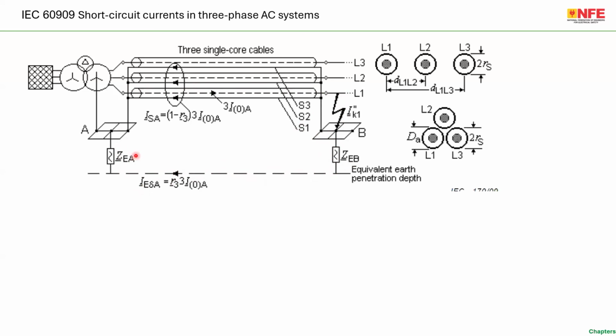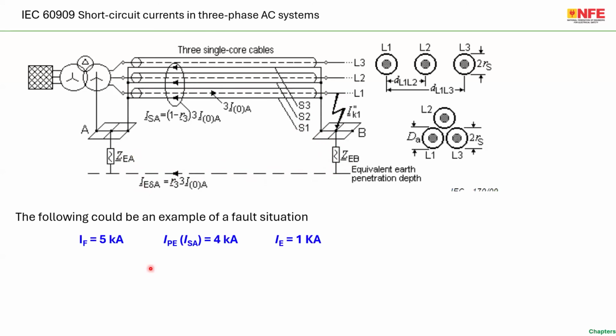So this is the only case, this is the only opportunity. Imagine, I'm just explaining an example. I will show you where you can find such information. Imagine the fault current is 5 kiloampere. The ISA, that means the current flowing through the shield conductor, is 4 kiloampere. Just for explaining to a not highly technical engineer, I use the word IPE, because in a lot of our presentations for low voltage we use the word IPE, the current through the protective earth conductor. Imagine that from station A to station B there is an overhead line with an earth conductor. Then 4 kiloampere goes through the earth conductor and about 1 kiloampere goes through the ZE, that means through the earth electrode. This is just an example.